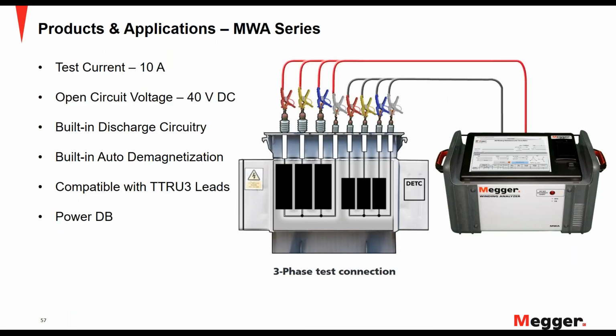Now, the next series of our products is the MWA series. The MWA series can output a current of up to 10 amps and has an open circuit voltage of 40 volts DC. It of course has a built-in discharge capability and auto demagnetization. So you don't physically have to change the magnitude or polarity as was done many years ago, which at that time might have been the available practice.